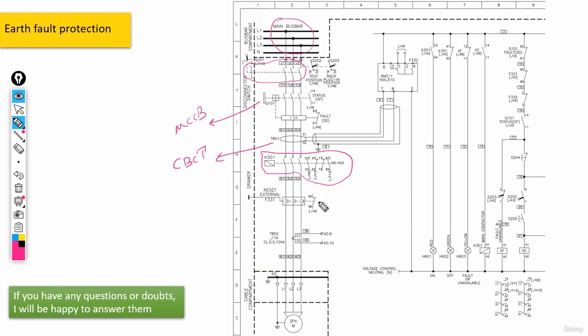Okay, what else? We have this overload relay, that's bimetal. And also we have the CBCT transformer signal that would be connected to the earth fault relay. And also, as I said, we have this normally closed contact set in the earth fault relay. And the address that we have for the terminal set in this contact would be 0/J9. Alright, and the address is actually pointing towards this point here. We talked about this before. Based on the zones, we have J9.